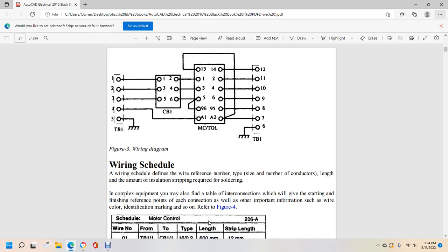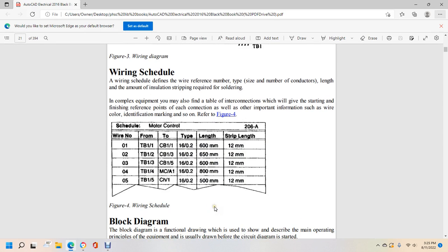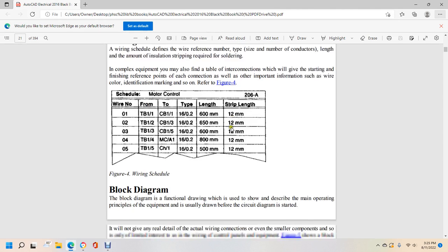Figure 3 shows a wiring diagram with some terminal boards and pins. Wiring scheduling is defined with the wire reference number, the type of wire, the number of conductors, the length, and the insulation strip length required, with soldering and crimping equipment. It must also be defined with a table of interconnection, which gives the starting reference point of each connection, as well as other important information such as the wire color, identification marking, and so on. Refer to Figure 4. The wiring schedule shows the wire number, from, to, the type, the length, and the strip length, and the motor control, and the number would be 206A.